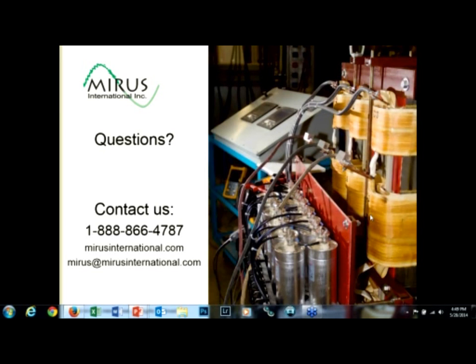There's another question here about voltage boost. It's asking if there's a problem with a voltage boost on the lineators. There is a slight voltage boost, but we make sure that it's between 2 to 3% maximum between the input and the output, and that occurs under no load conditions. This is typically not a problem for the variable speed drives. The only time it might be is if the maximum voltage rating of the drive is already being exceeded or approached. But this voltage boost is much less than what you would have with other competitive filters.